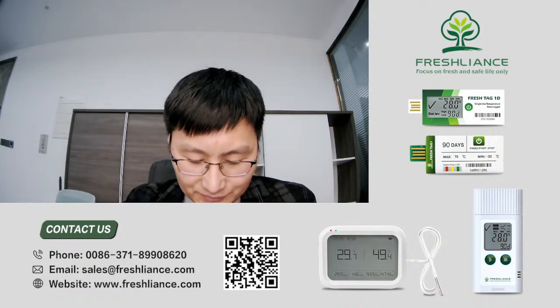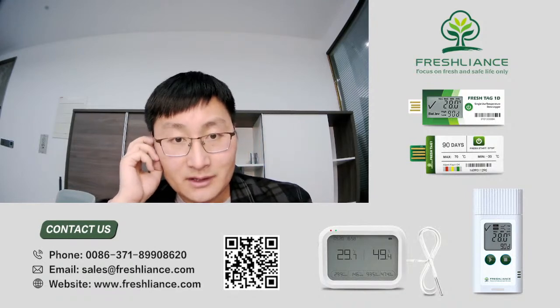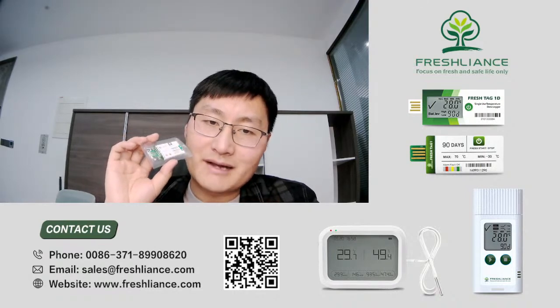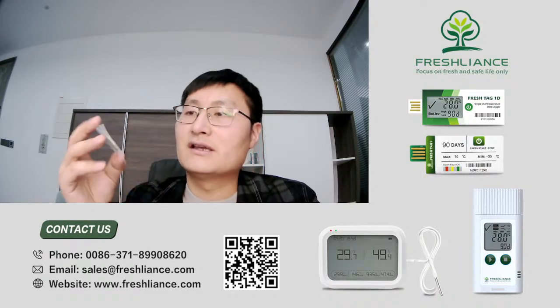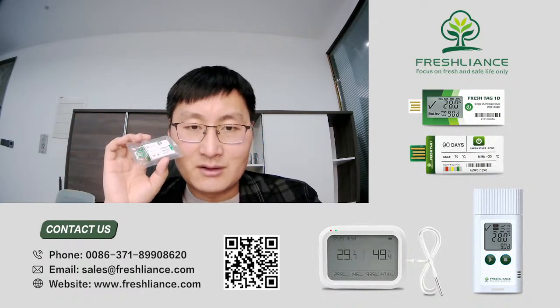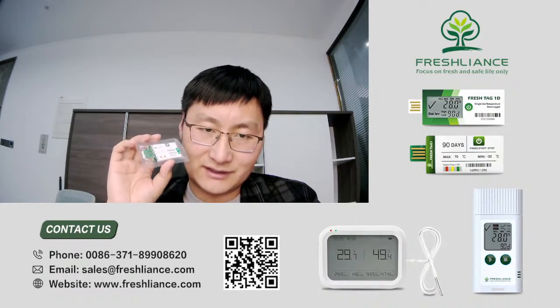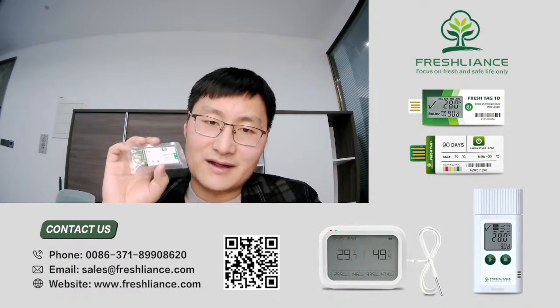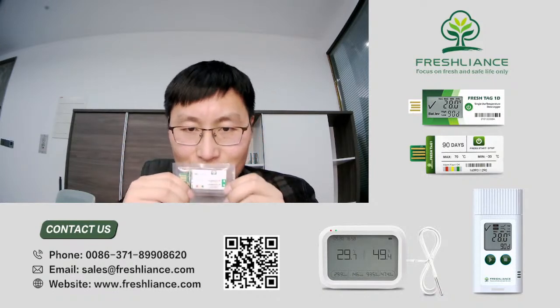And okay, for the specification, I can tell you one by one. Its temperature range, normally it is minus 30 to 70 degrees, and for some special requirements, we can also make it from minus 40 to 70 degrees. And its temperature accuracy is plus minus 0.5 degree at full temperature scale.